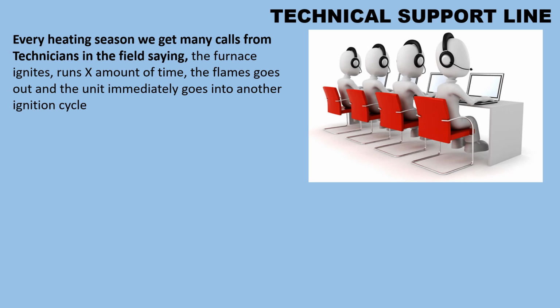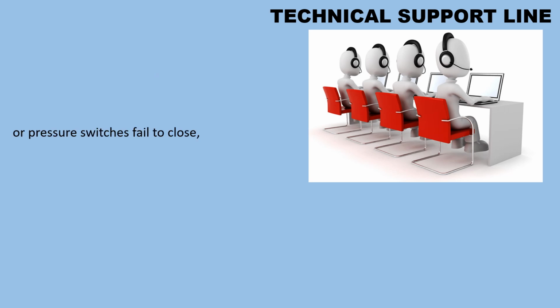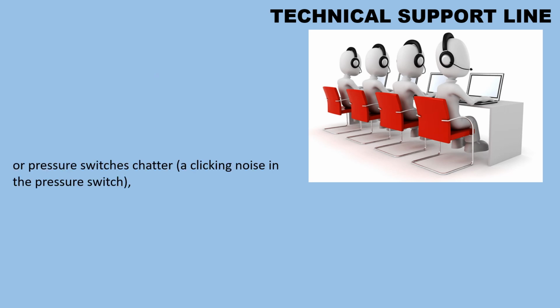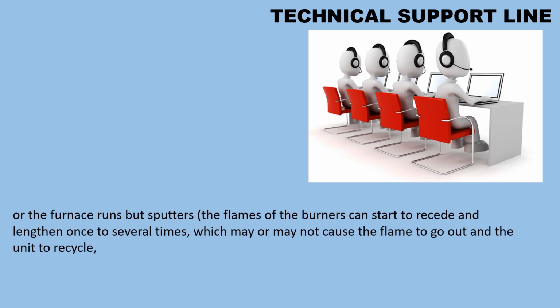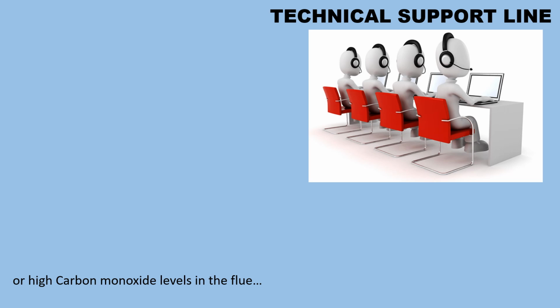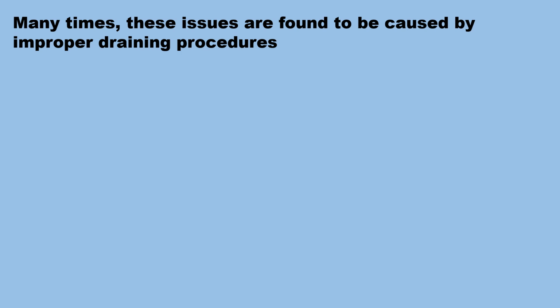Every heating season, we get many calls from technicians in the field saying the furnace ignites, runs X amount of time, the flame goes out, and the unit immediately goes into another ignition cycle. Or pressure switches fail to close, or pressure switches chatter, a clicking noise in the pressure switch. Or the furnace runs but sputters. The flames of the burners can start to recede and lengthen once to several times, which may or may not cause the flame to go out and the unit to recycle. Or high carbon monoxide levels in the flue. Many times these issues are found to be caused by improper draining procedures.